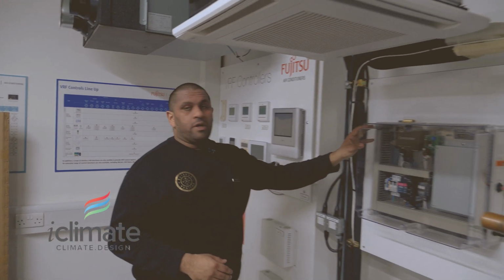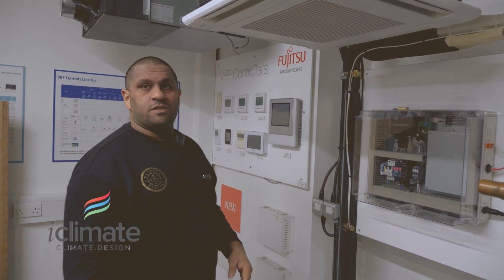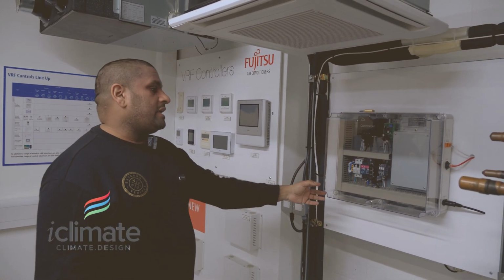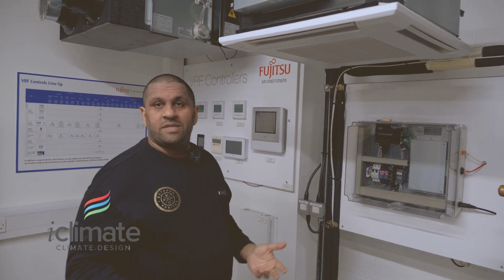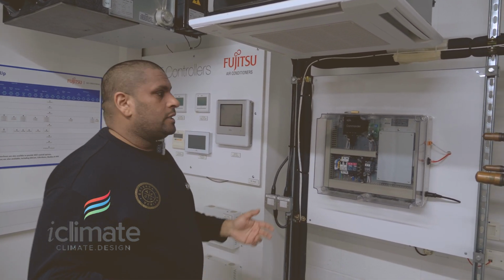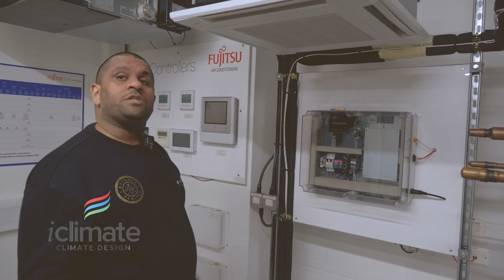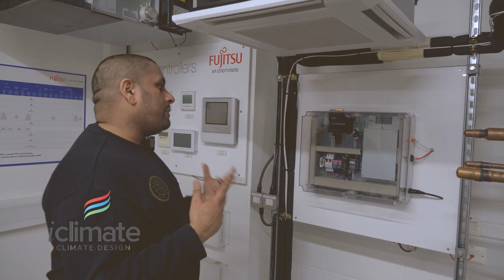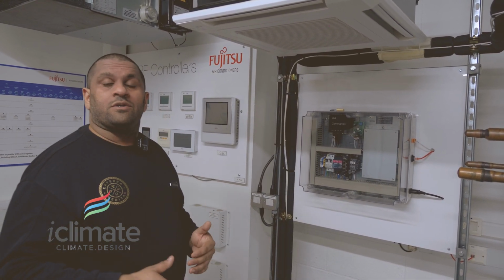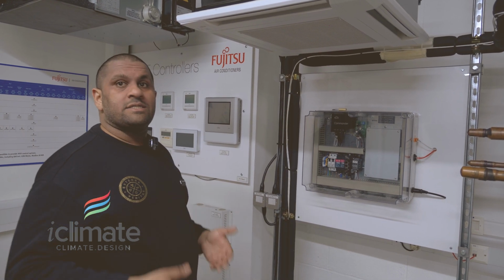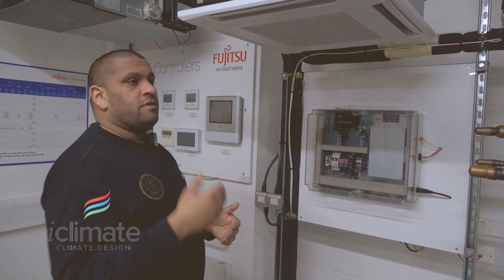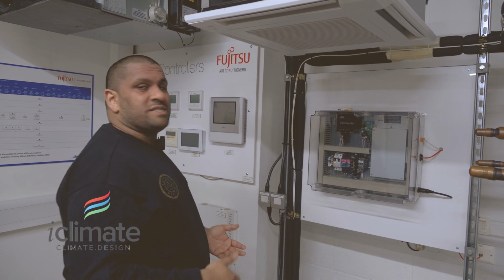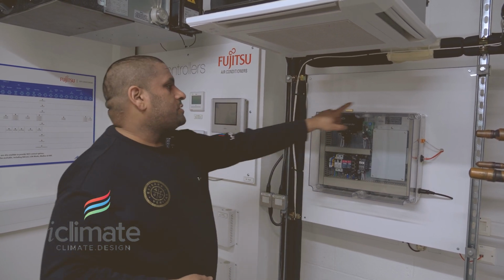The last point of control is the BMS integration, right? So when you have a large commercial building, and obviously you would have a BMS system, whether it be Trend or Honeywell, integrating the air conditioning is a key part of that. So you can have BMS control from your BMS to control the air conditioning, to set air handlers, dampers, chiller temperatures, VRF operating temperatures, indoor unit statuses in the rooms. And you do this through this integration panel.